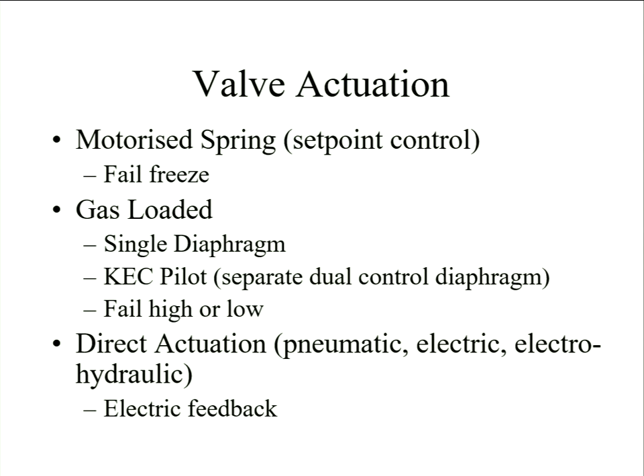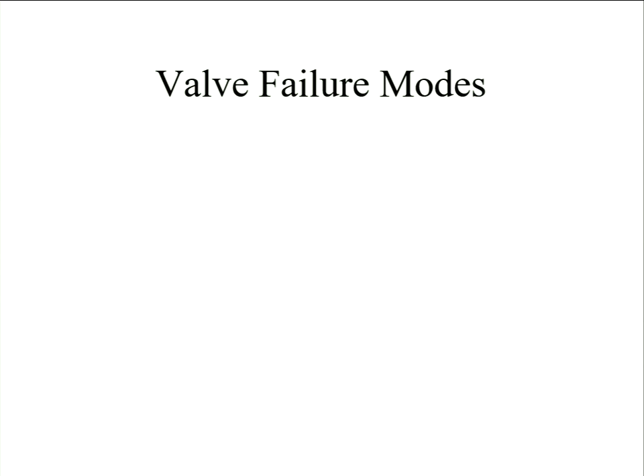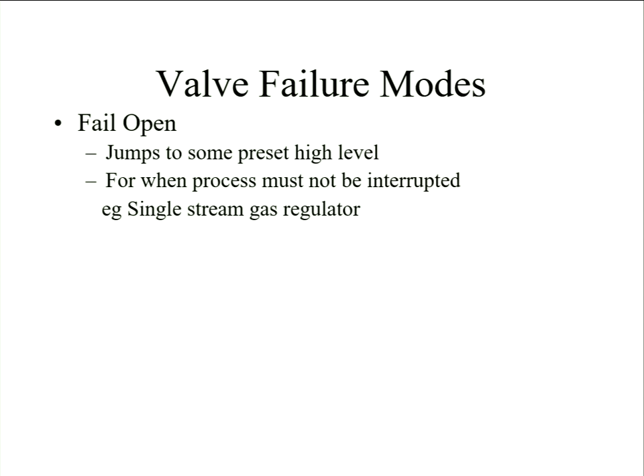Alternatively, it might be that really the safest thing, so I think we were talking about gas quality measurement. So let's say you have a sour gas feed, high H2S in your gas, and you don't want that to get in your pipeline because you worry about stress corrosion cracking. In that particular instance, you'd rather lose production and protect the pipeline against integrity issues arising from H2S ingress into the system. And fail freeze, it'll leave it where it is, but you might need to put some extra high pressure, low pressure protection. Valves themselves can have different characteristics.